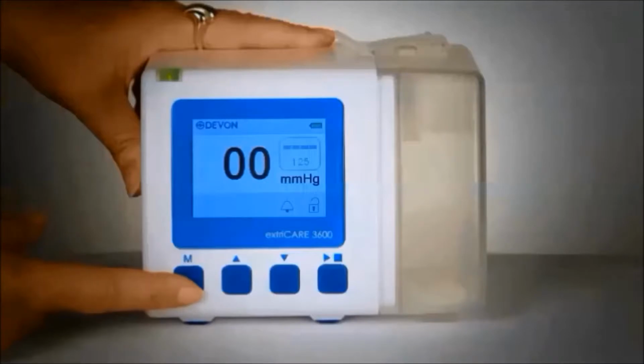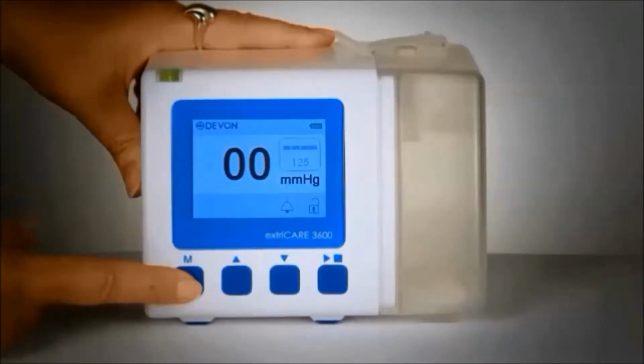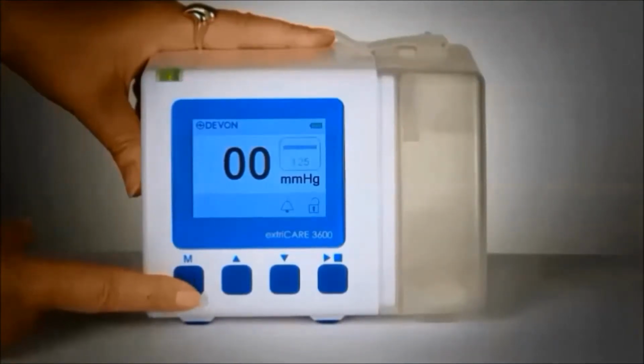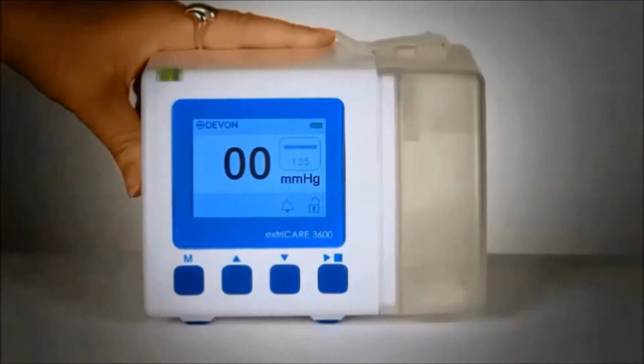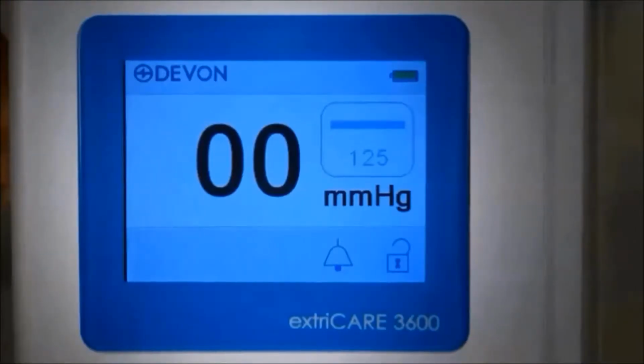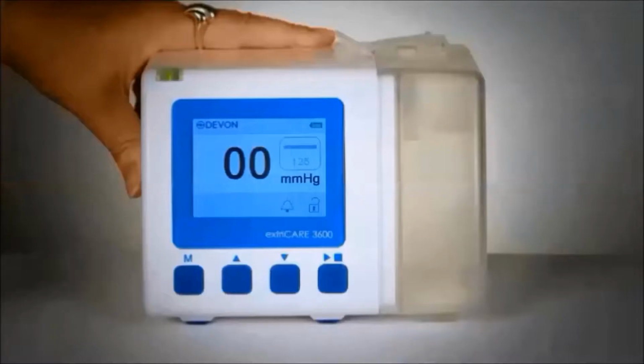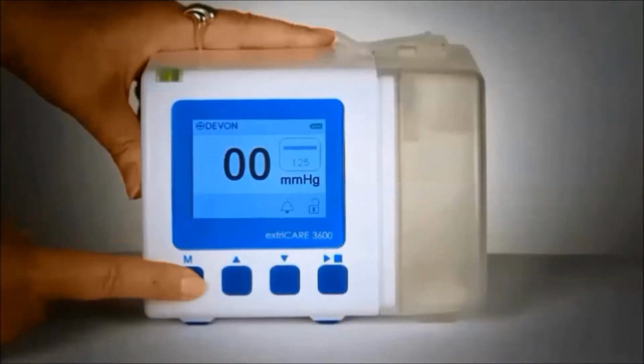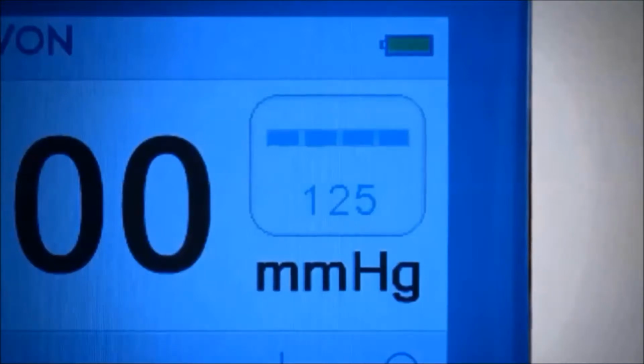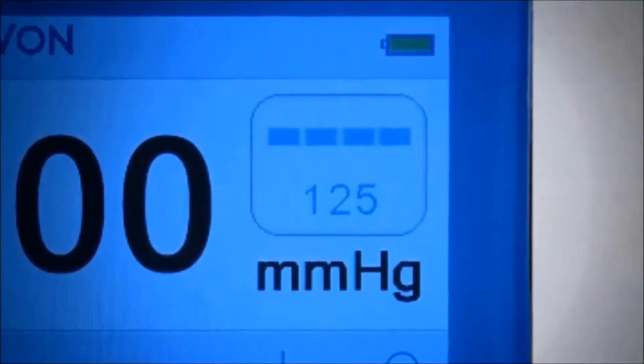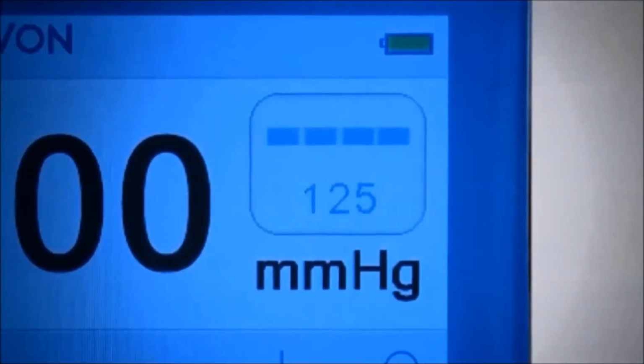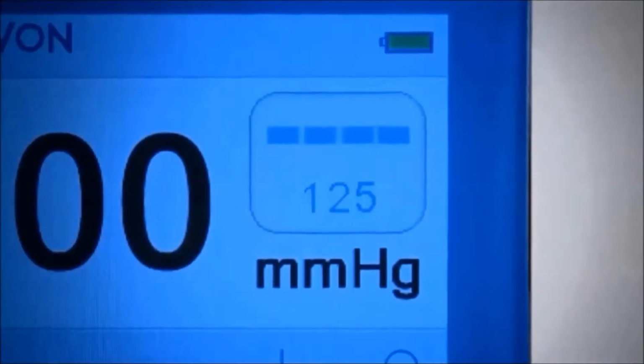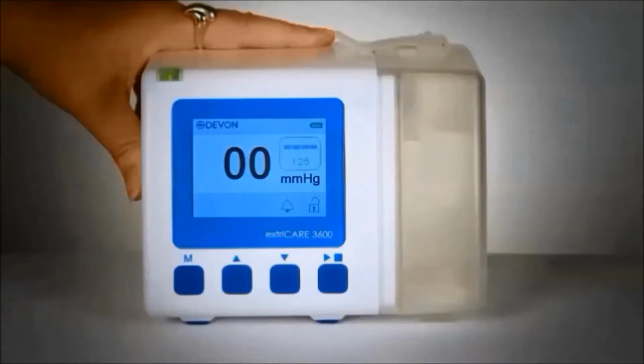The extriCARE 3600 can operate in continuous or intermittent mode. If operating in continuous mode, a solid line will be displayed on the screen and the device will operate at the pressure set by the user. If the device is operating in intermittent mode, a dashed line will be displayed on the screen and the extriCARE 3600 will operate for 5 minutes at the set pressure, for 2 minutes at 20 millimeters of mercury, and then will repeat.